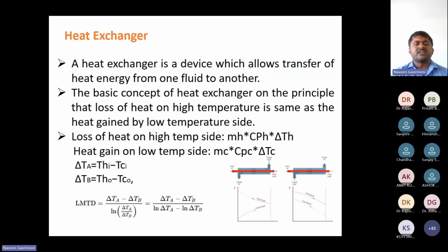So this is the heat exchanger. Another part is the heat exchanger. Why is the heat exchanger concept more important? Because all our accessories like economizer, superheater, evaporator, and the HP heaters depend on this heat exchanger concept. As we know, we have three types of flows: parallel flow, counter flow, and cross flow. Now in our plants we are using counter flow arrangement only. Performance depends on the LMTD.